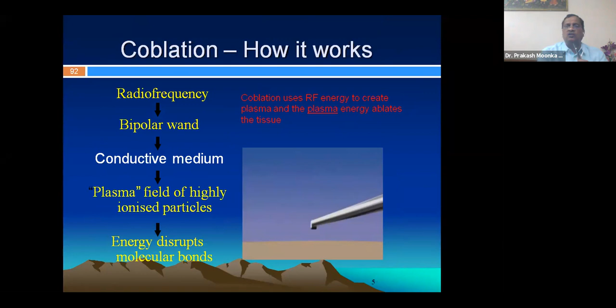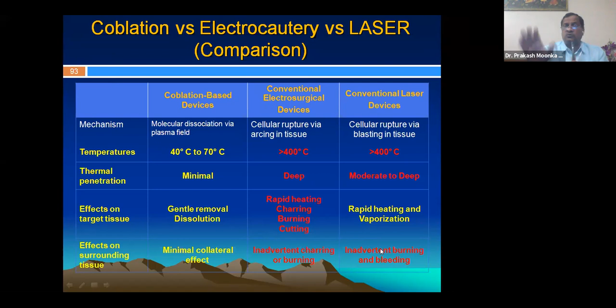If we compare coblation, conventional electrosurgery, and conventional laser, the main difference in mechanism is that coblation works by dissociation by plasma field. Electrosurgery causes cellular rupture by arcing in tissue. In laser also, cellular rupture by blasting the tissue. Temperature is the major advantage in coblation. Thermal penetration is minimum, whereas in the others it is moderate to deep. The effect on target tissue is gentle removal, whereas it is rapid heating, charring, and burning in electrosurgery, and rapid heating and vaporization in laser. The effect on surrounding tissue is minimal collateral damage in coblation, inadvertent charring or burning in conventional electrosurgical devices, and inadvertent burning and bleeding in laser devices for tonsillectomy.